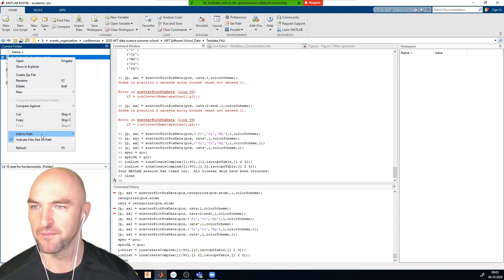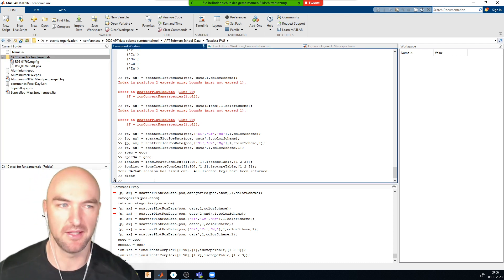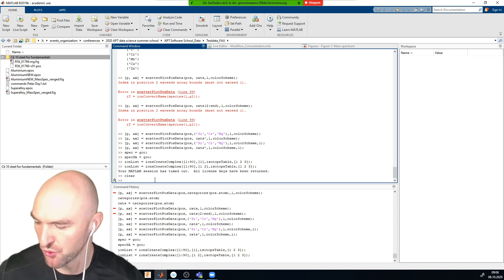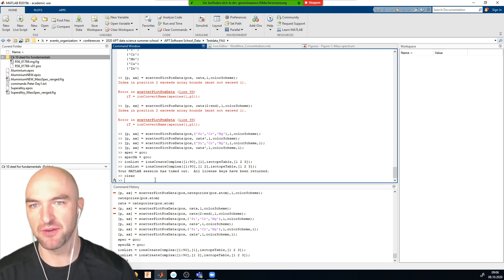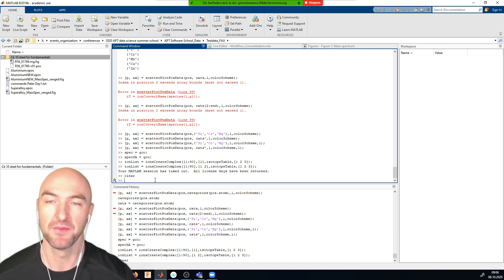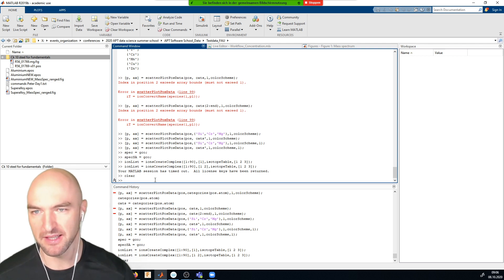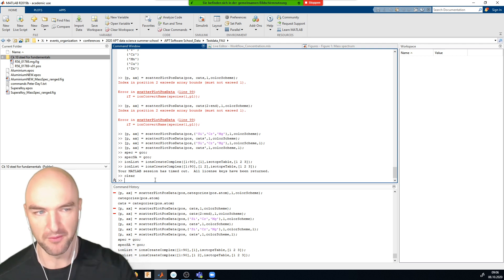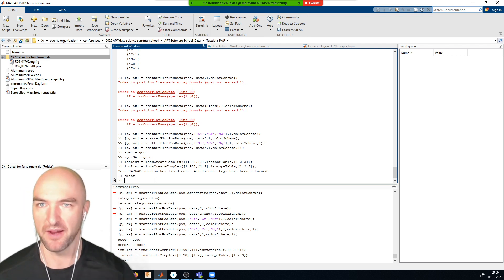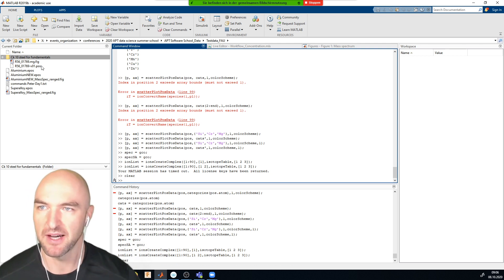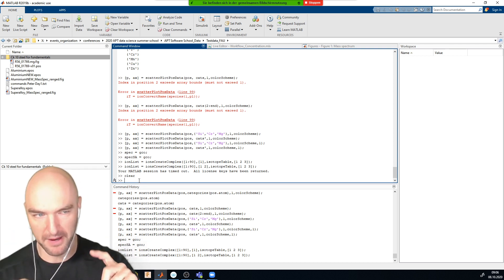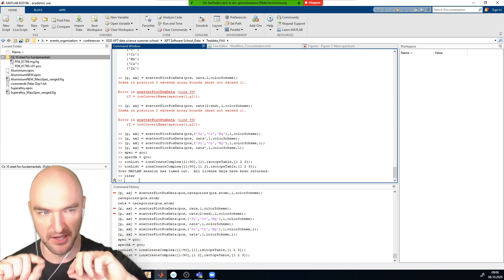Don't worry — you don't have this data and you don't need it. This is just for me to show some of the detector pileup issues we have with delay line detectors in general, which skew our data a little bit. Very often when you look at your atom probe data and the isotopic abundances don't quite fit the natural abundances, the reason is not that your material differs from Earth's natural abundance — it's that we have an isotope effect in detector pileups. I've taken a steel dataset because iron has isotopic distributions with minor and major isotopes.